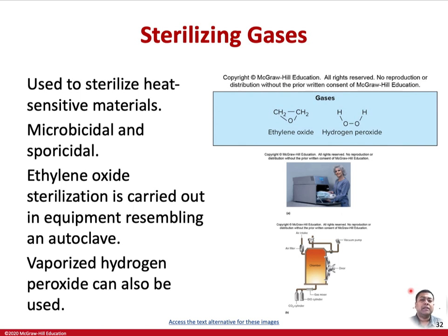On the other hand, the biological safety cabinets that we saw several pictures of can be decontaminated by using vaporized hydrogen peroxide. These are used at a wide variety of concentrations, between about 140 to 1400 parts per million, and that can also disinfect or decontaminate, but not sterilize. And it is pretty safe to use because the hydrogen peroxide is broken down into oxygen and non-toxic water.